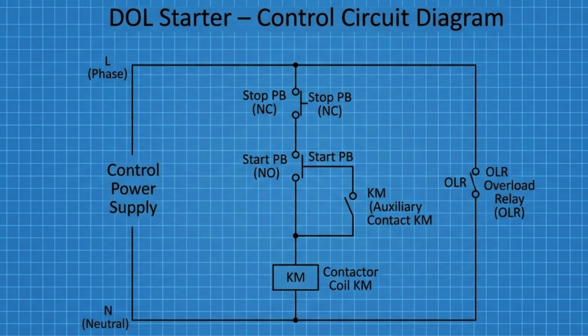When the operator presses the start button, the contact closes and allows current to flow to the contactor coil, which is usually labeled as KM in electrical diagrams. Once the contactor coil is energized, the contactor pulls in and closes its main contacts in the power circuit, allowing three-phase power to reach the motor. At the same time, an auxiliary contact of the contactor, which is also a normally open contact, closes and creates what is called a holding circuit or sealing circuit. This holding contact is connected in parallel with the start push button.